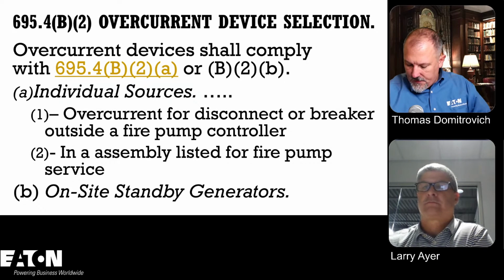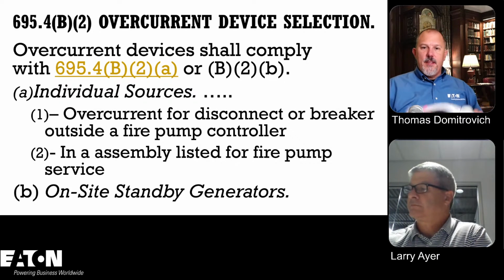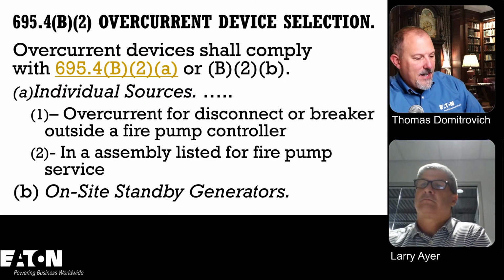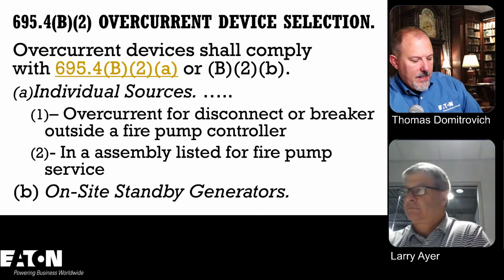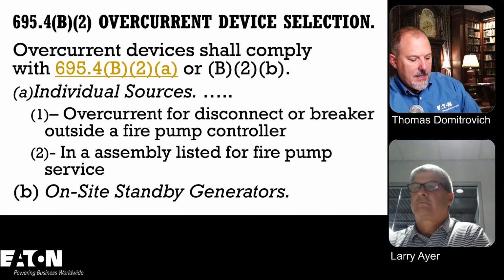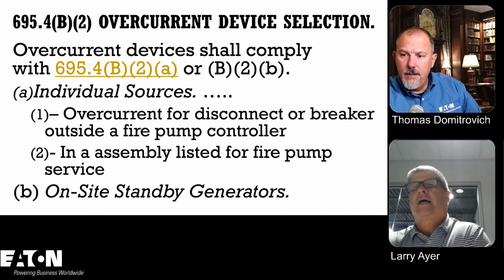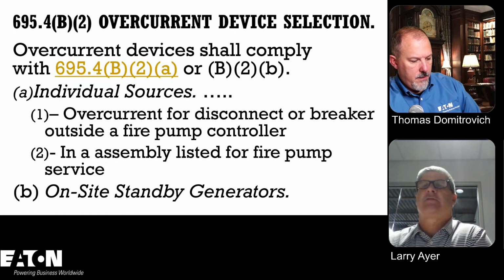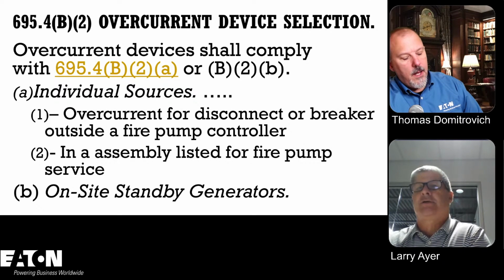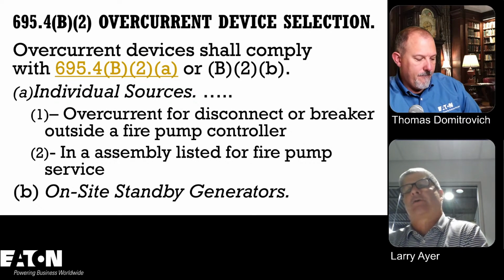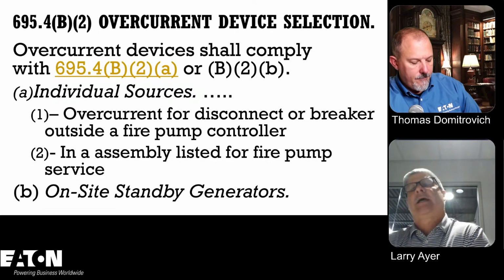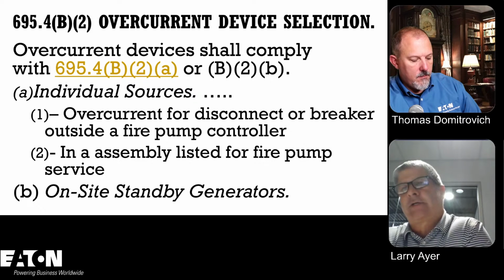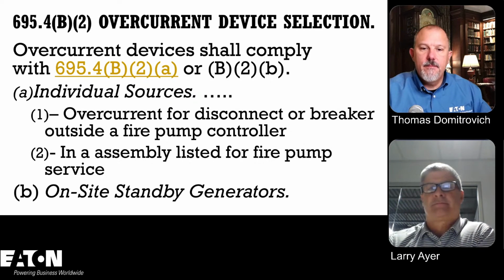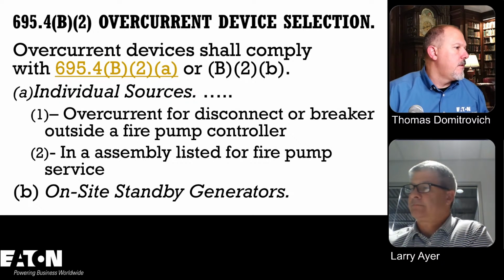It's almost as if it's a little bit of a problem with the code book because they grade out both areas. You have 1, 2. 2 has A, B, C, D, and all of a sudden there's a B on-site standby generator. I think that should be 3. No, I think they're just saying that if you have an individual source, here's what you've got to do. Yeah, because you want that locked rotor. So the one really is saying you have to handle the locked rotor in A, and B is saying you don't really need to worry about the locked rotor. Gotcha. All right. Good one.